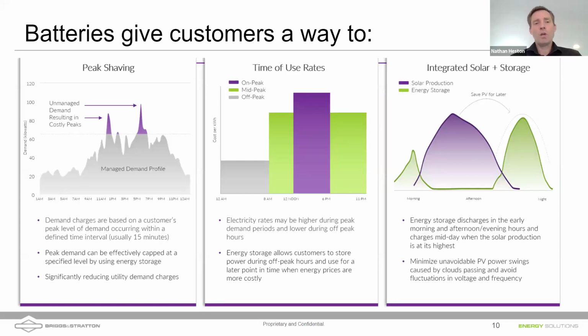In other words, if you're getting demand charges from your utility for going over a certain number of kilowatts for your facility, you could supplement the power going to your loads with an inverter, exporting some amount of energy to that loads panel when demand rises. You do that by monitoring how much power is coming in using CTs, and then try to limit the power you're pulling from the grid.